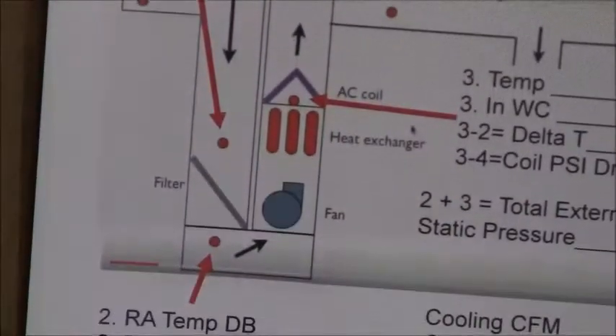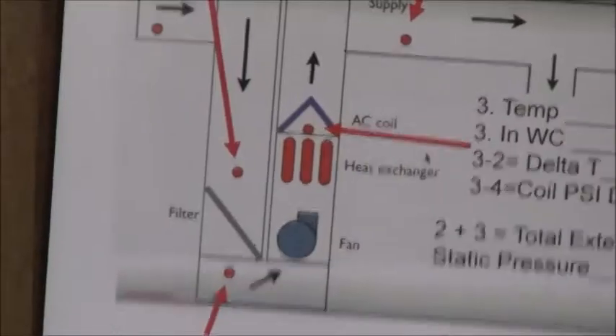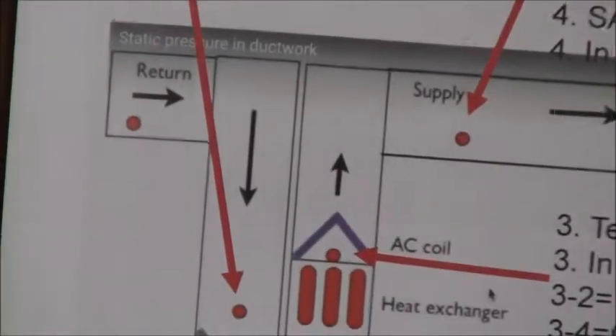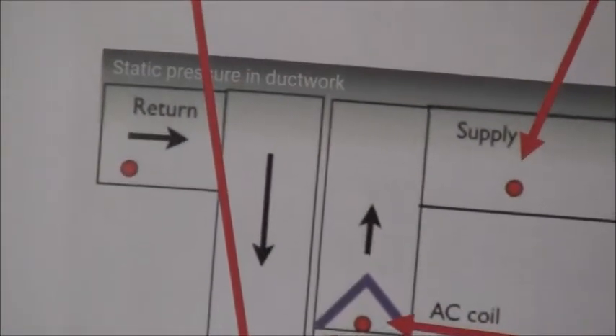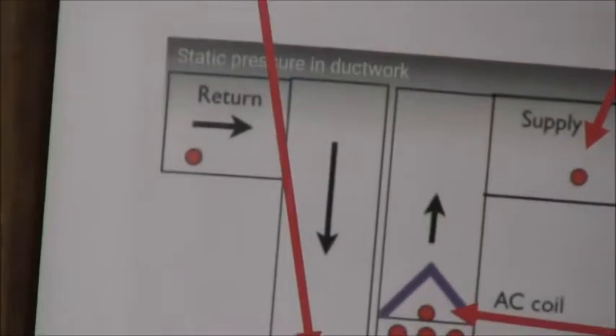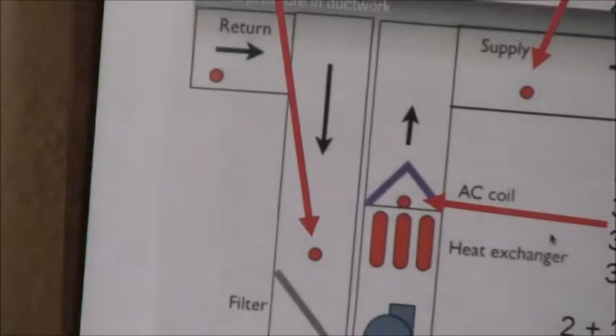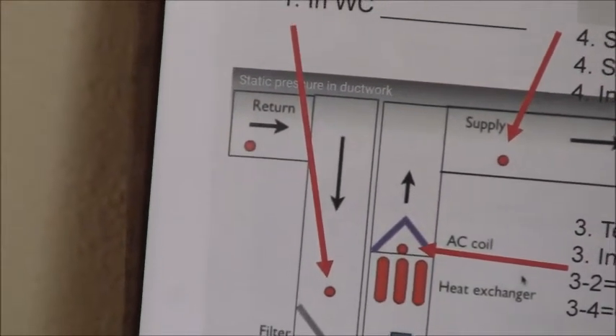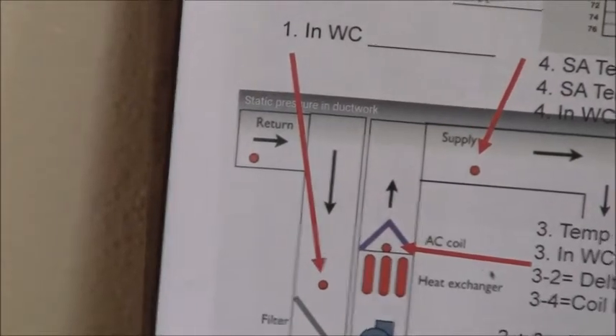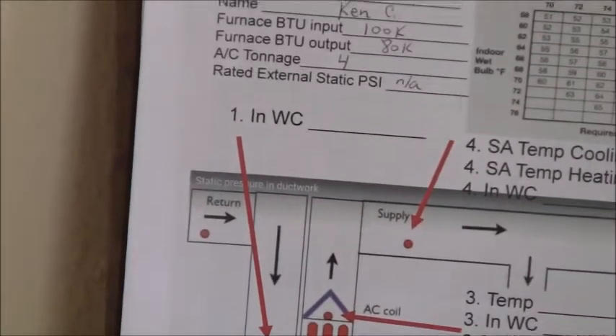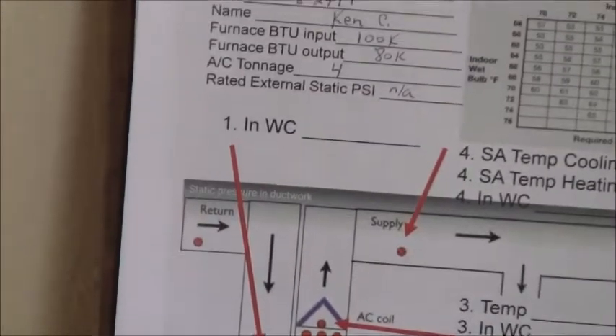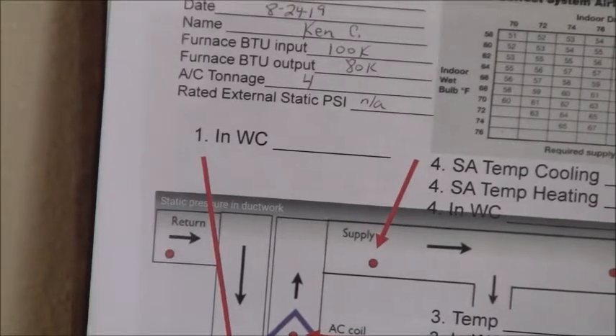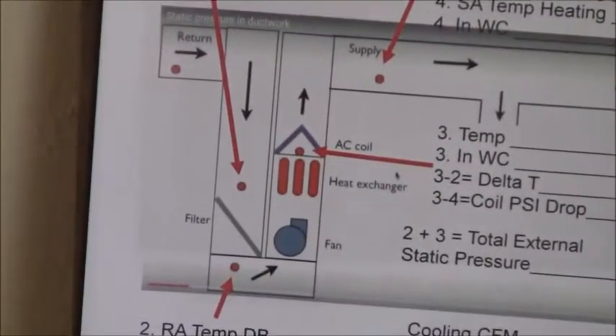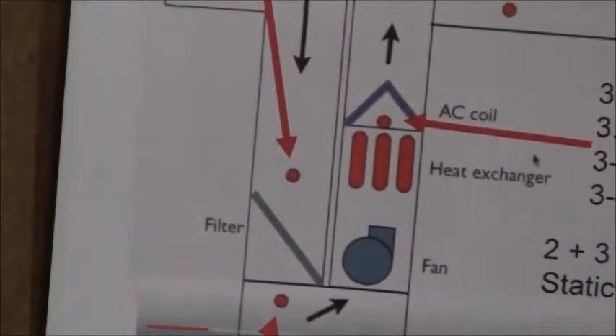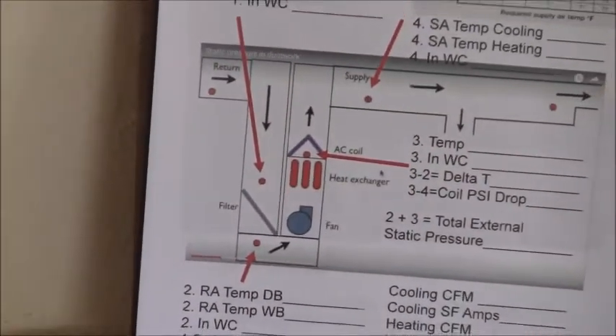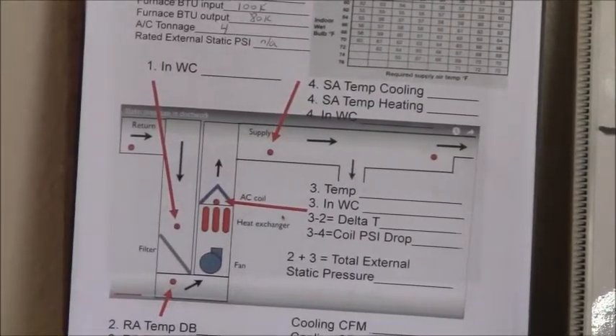You can see I've got a picture of an HVAC system. You've got the return air coming in, coming down the return duct right there. You can see the arrows. And the red dots are where sample points are located, and on some of the red dots I've numbered them. So this first sample point, which is just before the filter on the return duct, is point number 1. And then inches of water column is how much static pressure is at that location before the filter. So I'm trying to determine exactly what's going on in the ductwork and to see how well this system is breathing.